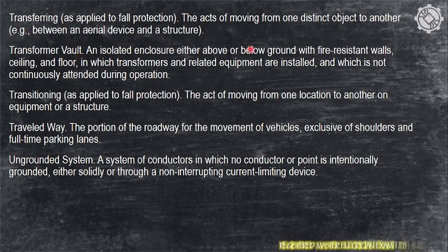It could be below ground or underground. Then certain conditions must be met. The walls must be fire resistant, the ceiling and the floors, no? The minimum fire resistant rating for transformer vaults and other electrical vaults is 3 hours. Ibig sabihin, 3 hours pa bago siya completely ma-engulf in flame o masunog yung buong transformer vault or the vault itself.